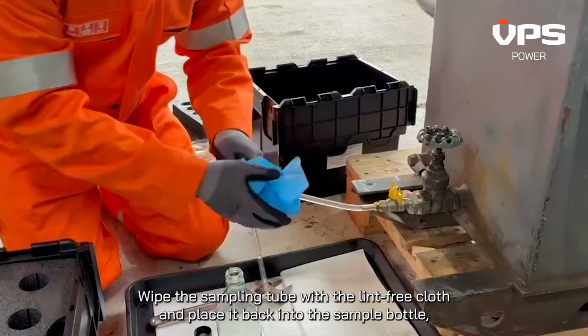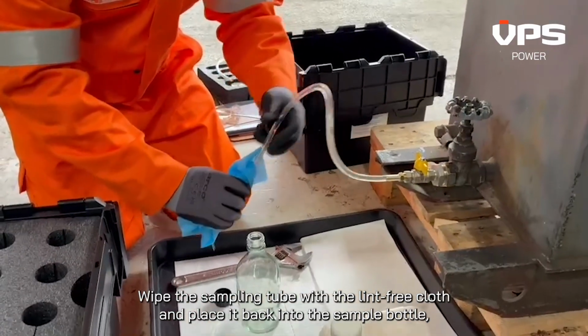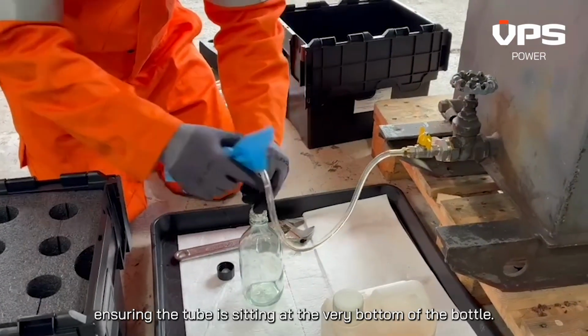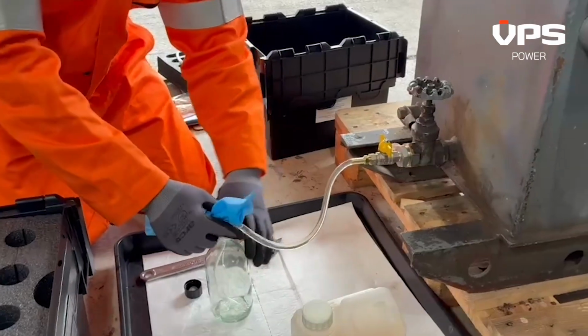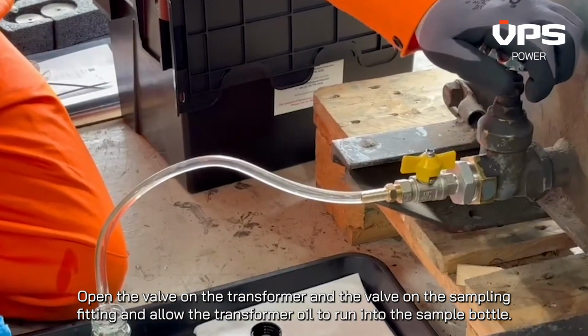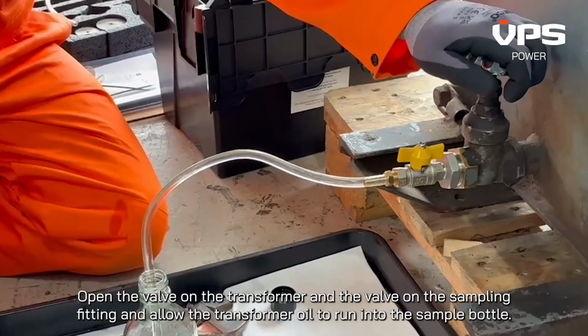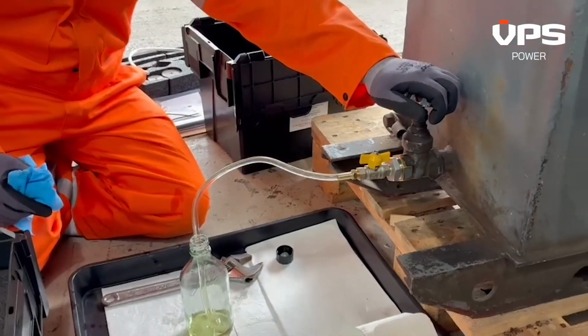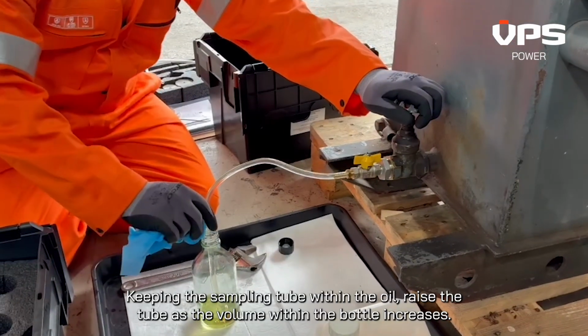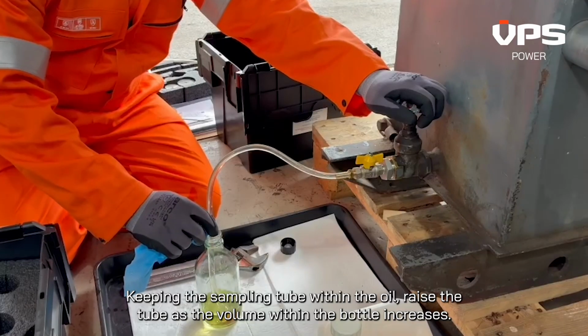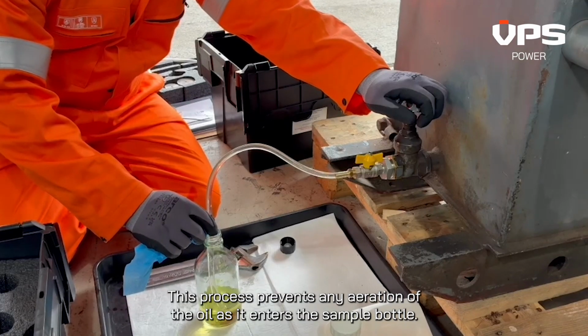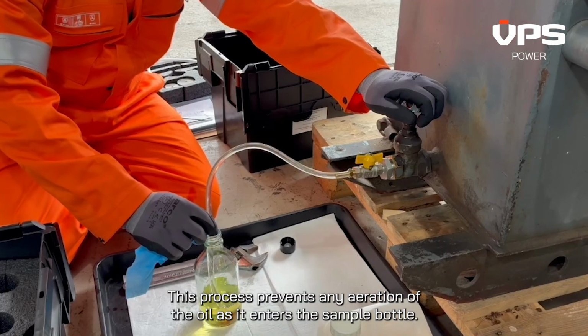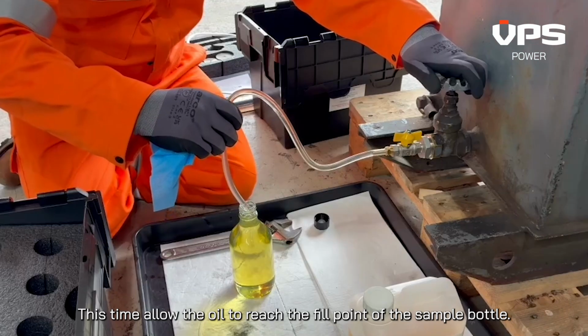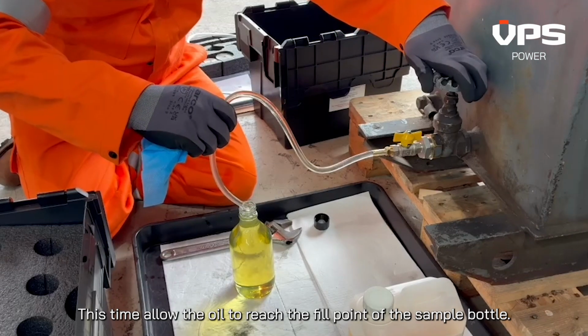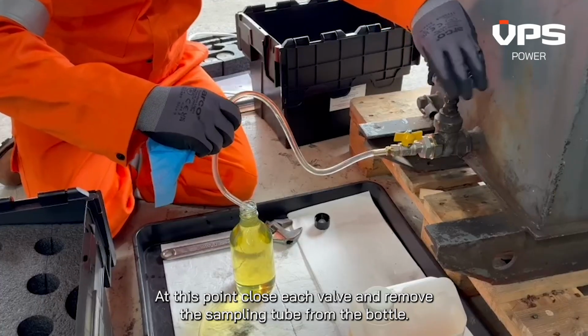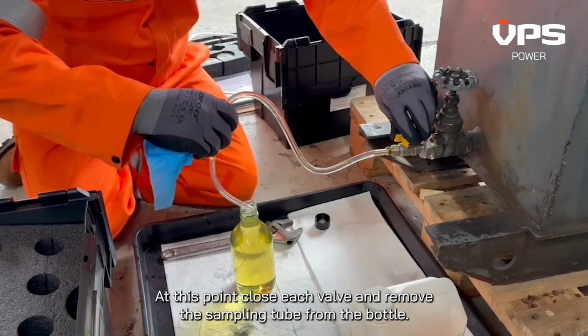Wipe the sampling tube with the lint-free cloth and place it back into the sample bottle, ensuring the tube is sitting at the very bottom of the bottle. Open the valve on the transformer and the valve on the sampling fitting and allow the transformer oil to run into the sample bottle. Keeping the sampling tube within the oil, raise the tube as the volume within the bottle increases. This process prevents any aeration of the oil as it enters the sample bottle. This time allow the oil to reach the fill point of the sample bottle. At this point, close each valve and remove the sampling tube from the bottle.